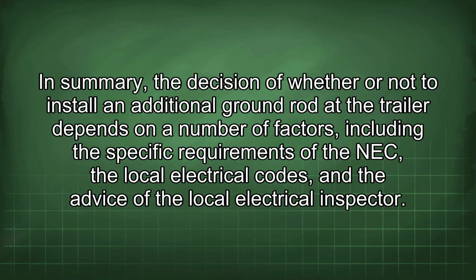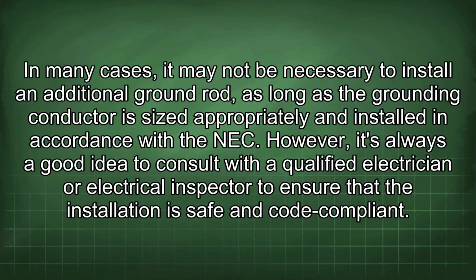In summary, the decision of whether or not to install an additional ground rod at the trailer depends on a number of factors, including the specific requirements of the NEC, the local electrical codes, and the advice of the local electrical inspector. In many cases, it may not be necessary to install an additional ground rod, as long as the grounding conductor is sized appropriately and installed in accordance with the NEC. However, it's always a good idea to consult with a qualified electrician or electrical inspector to ensure that the installation is safe and code compliant.